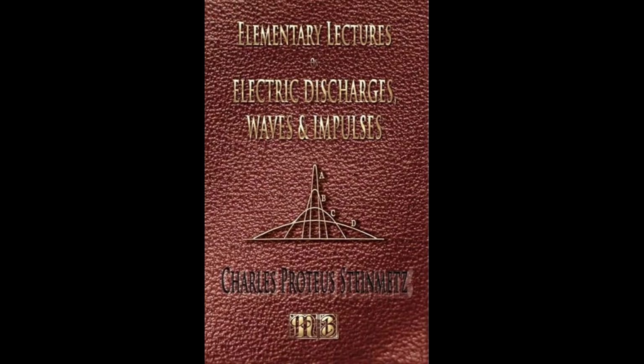The armature currents I1, I2, I3 are proportional to the field flux which produces them, and thus gradually decrease, from initial values, which are as many times higher than the final values as Φ is higher than Φ0, or M times, and are represented in Figure 21b. The resultant MMF of the armature currents, or the armature reaction, is proportional to the currents, and thus follows the same field transient, as shown by F in Figure 21c.